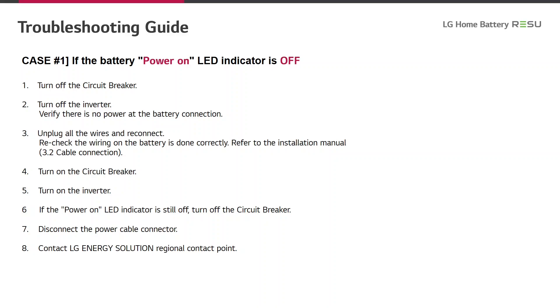Case number 1: the battery Power on LED indicator is off. Turn off the circuit breaker, then turn off the inverter. Verify there is no power at the battery connection. Unplug all the wires and reconnect, checking that the wiring on the battery is done correctly — refer to the installation manual. Turn on the circuit breaker again, then turn on the inverter again. If the Power on LED indicator is still off, turn off the circuit breaker, disconnect the power cable connector, and contact LG Energy Solution regional contact point.